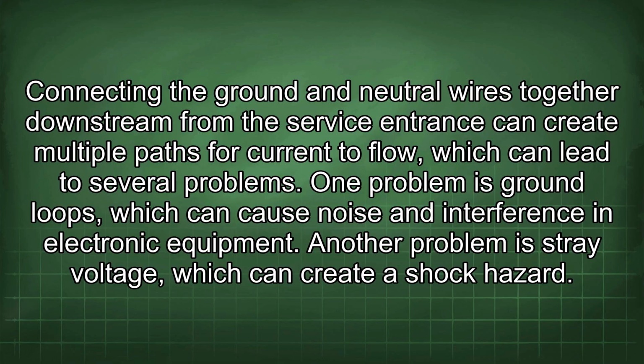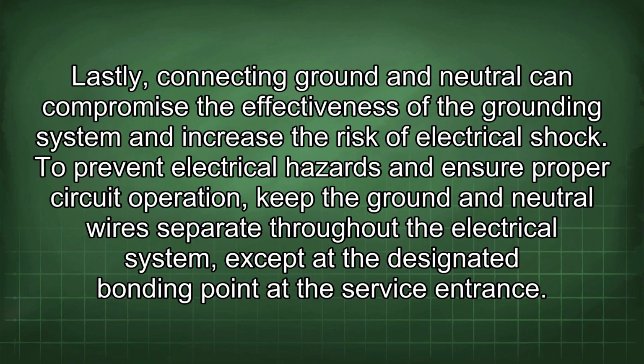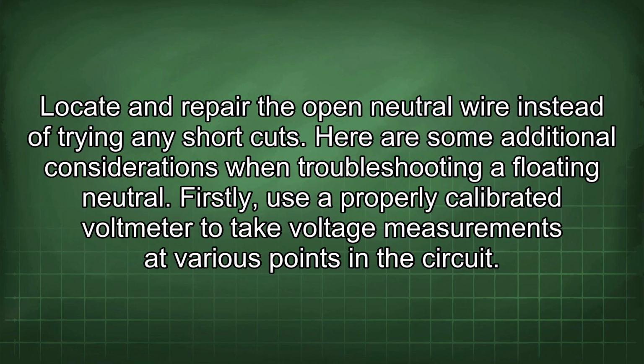One problem is ground loops, which can cause noise and interference in electronic equipment. Another problem is stray voltage, which can create a shock hazard. Lastly, connecting ground and neutral can compromise the effectiveness of the grounding system and increase the risk of electrical shock. To prevent electrical hazards and ensure proper circuit operation, keep the ground and neutral wires separate throughout the electrical system, except at the designated bonding point at the service entrance. Locate and repair the open neutral wire instead of trying any shortcuts.